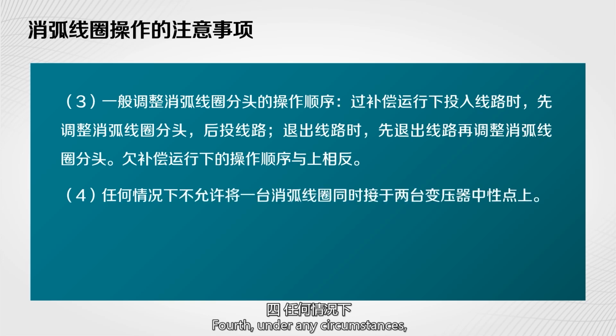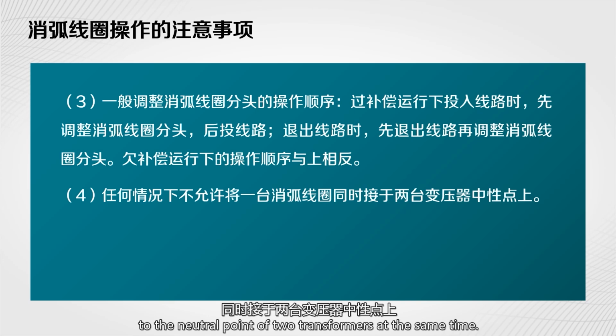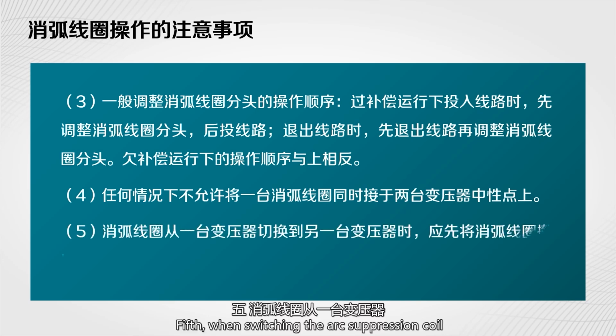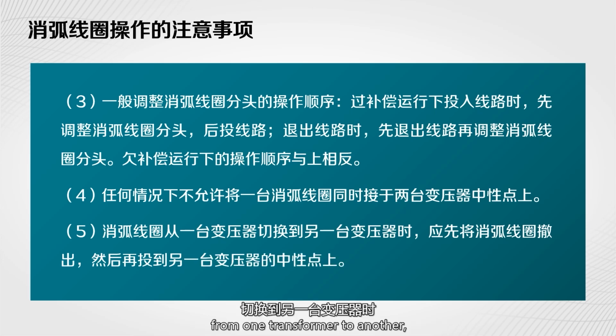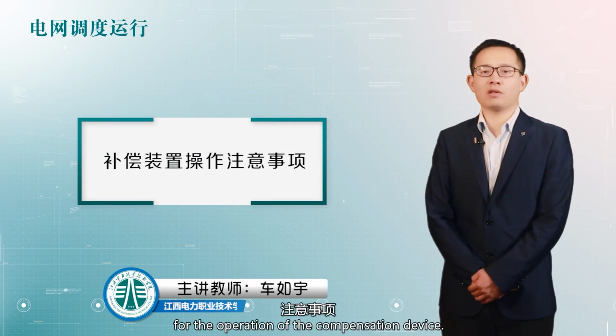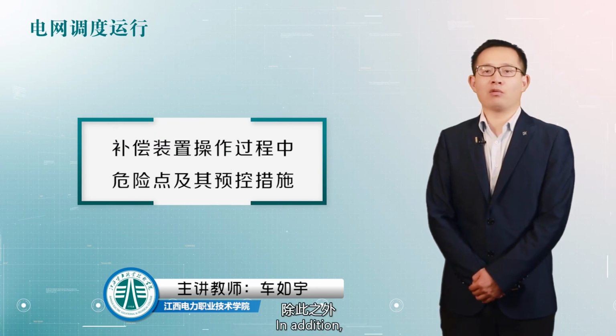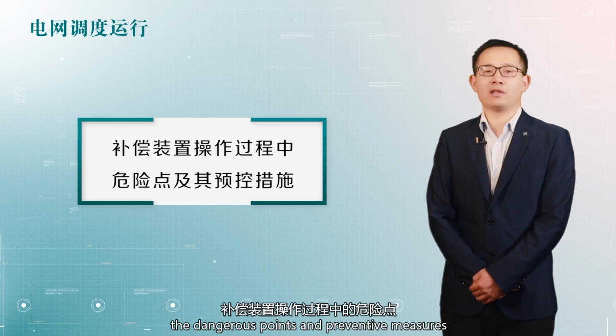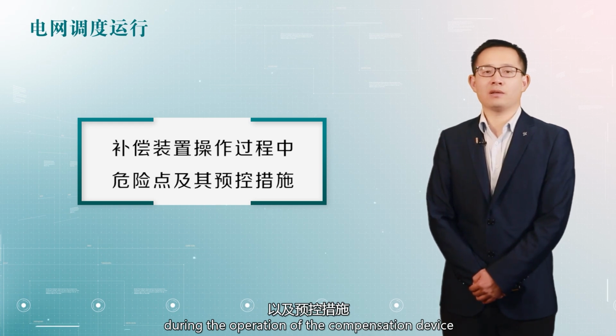Fourth, under any circumstances, it is not allowed to connect one arc suppression coil to the neutral point of two transformers at the same time. Fifth, when switching the arc suppression coil from one transformer to another, the arc suppression coil should be withdrawn first and then put into the neutral point of the other transformer. Previously, we have learned the precautions for the operation of the compensation device. In addition, we also need to master the dangerous points and preventive measures during the operation of the compensation device.